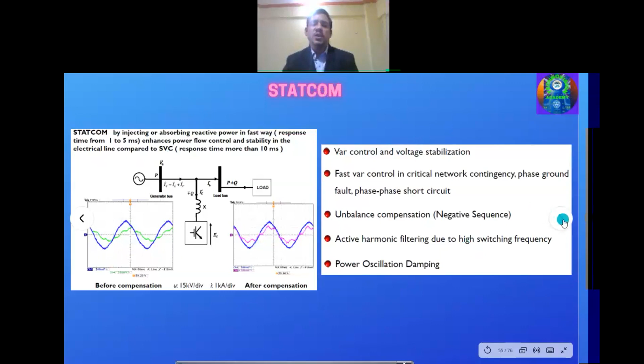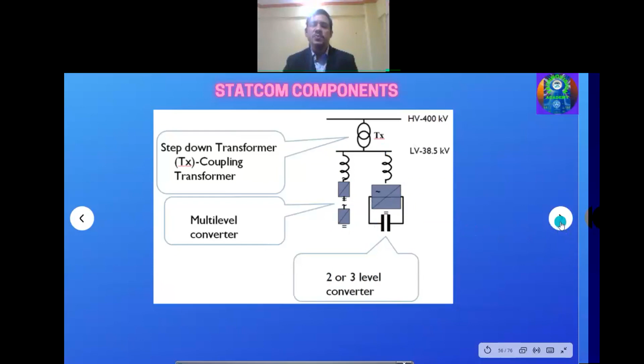STATCOM also, similarly, we can connect with the power system. We have the EHV level, then a step down transformer, or we can call it a coupling transformer also. And this is a bus where you connect the voltage source converter through the reactor, and here is a capacitor bank connected on the DC side. And here, multi-level converters: if I want to enhance the rating of the VSC, then I have to use multi-level converters to achieve a particular rating. It might be 2 or 3 level converters used to achieve that rating. So these are the STATCOM components.